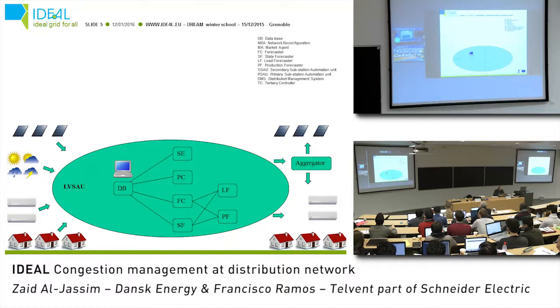The state estimation algorithm and so on. The database gets some input from different smart meters or weather data from distributed generations in the low voltage network, and of course these will not be full data for all the nodes in the network. So we have a state estimation algorithm to evaluate the state of the network. And we have power control algorithms, state forecasting algorithms that also use an input from two other algorithms, what we call the load forecaster and the production forecaster, that forecast the load in the distribution network and the production of the distributed energy resources in the low voltage network.